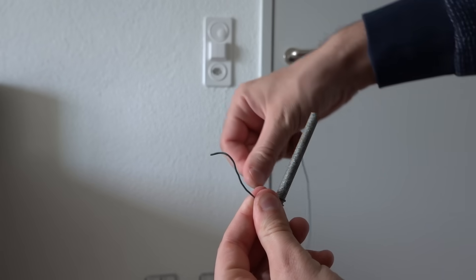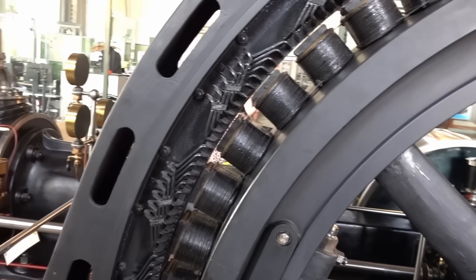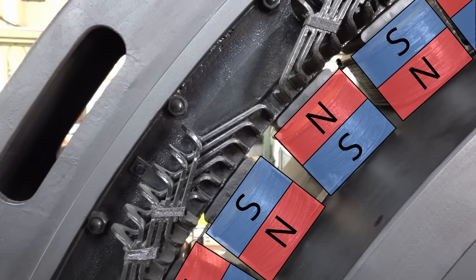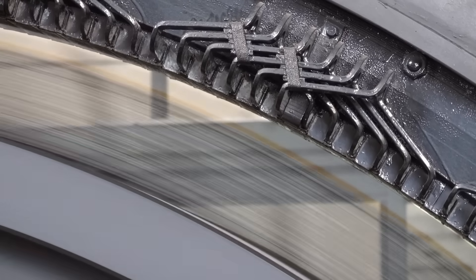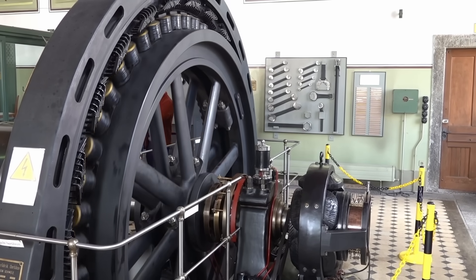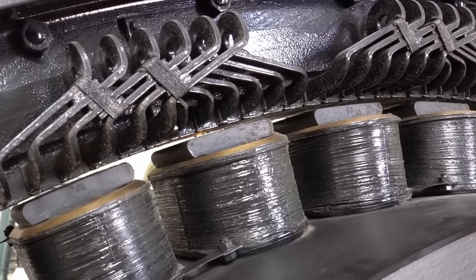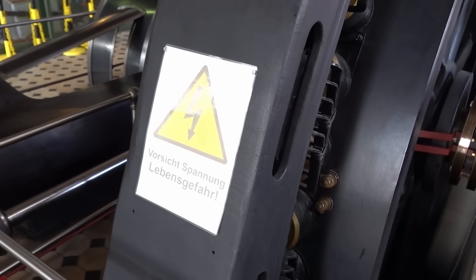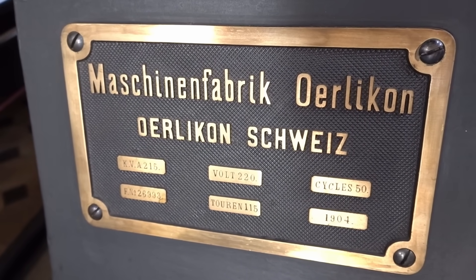Luckily, we can use another electrical trick from school. Wrap a wire around a core, run DC power through it, and you have an electromagnet. For now, let's ignore where that DC power comes from and instead just observe the coils. As you can tell from the interconnections between them, each coil is wired in reverse to the other, causing them to be of opposite polarity each. So unlike our little permanent magnet, this rotor here has a multitude of north and south poles when powered with DC. When it is at speed, it rotates such that at any given point in the stator, 100 poles pass by every second. Since they're alternating between north and south pole, this equals 50 Hz, which is the frequency of Switzerland's power grid. A big advantage of the rotor's poles consisting of electromagnets instead of permanent ones is that their power can be regulated. When running more DC power through the poles, their magnetic field becomes stronger and the AC generator thus produces a higher voltage. This way, the much smaller DC current can be used to control the much larger AC output of the generator.